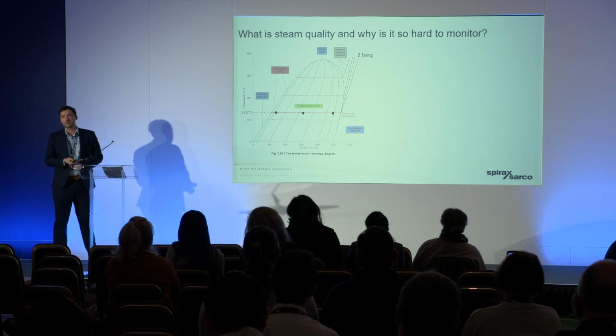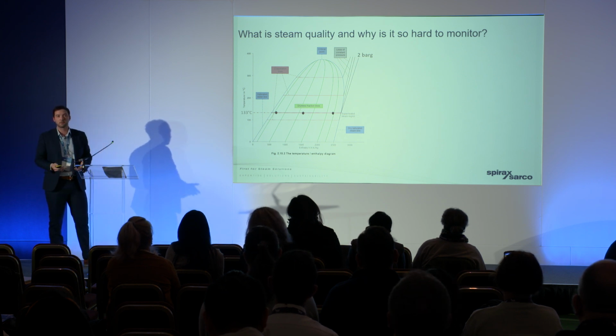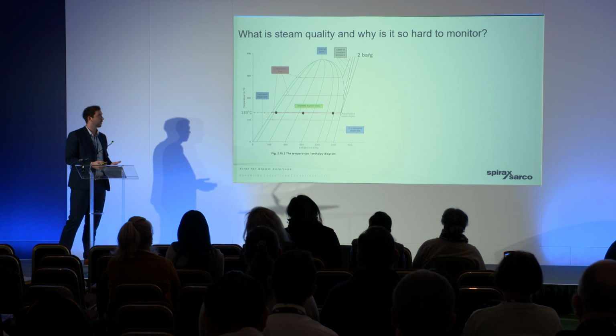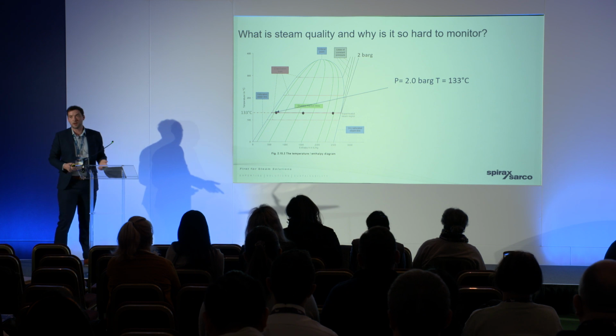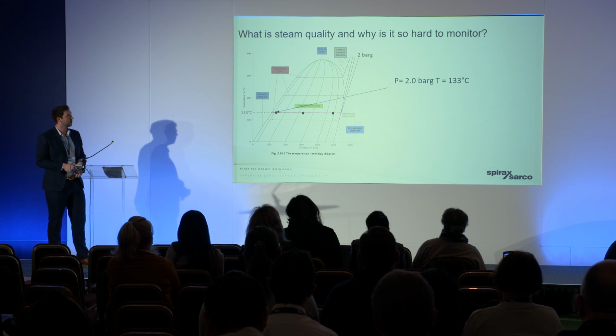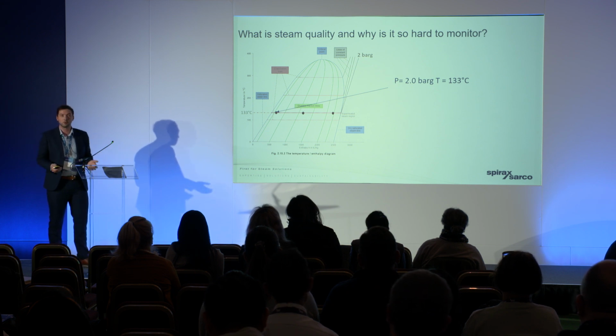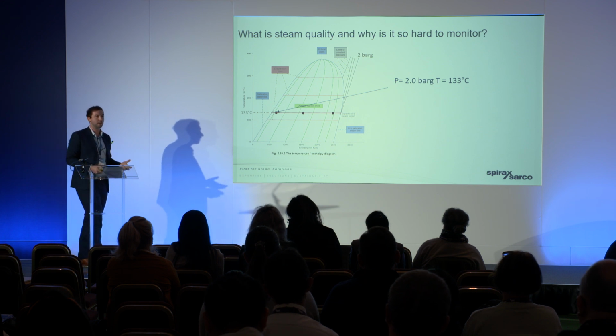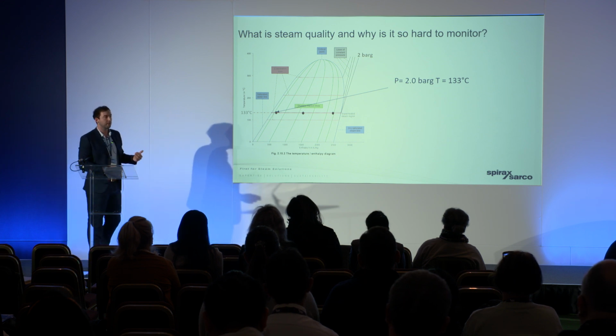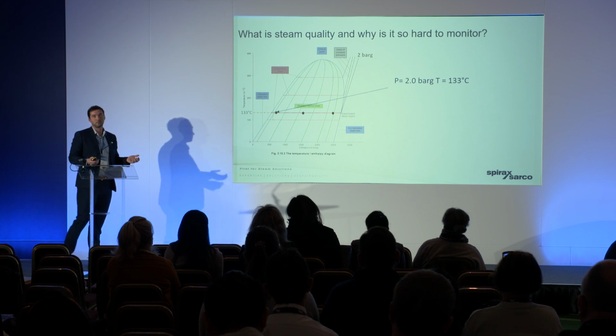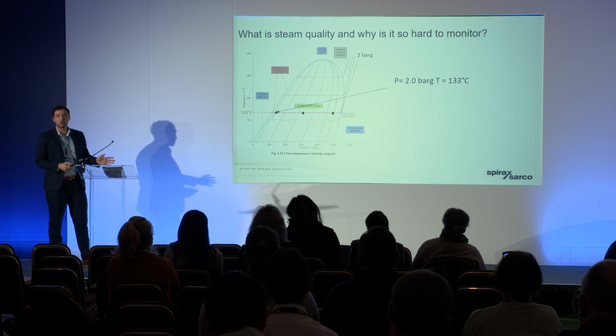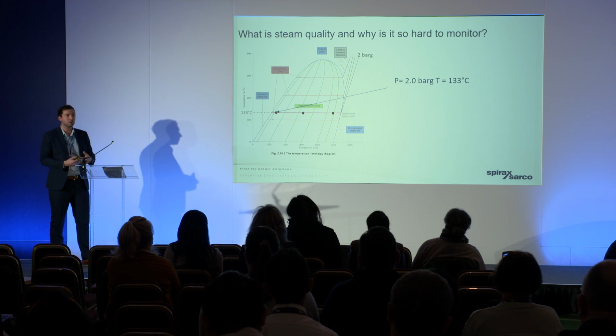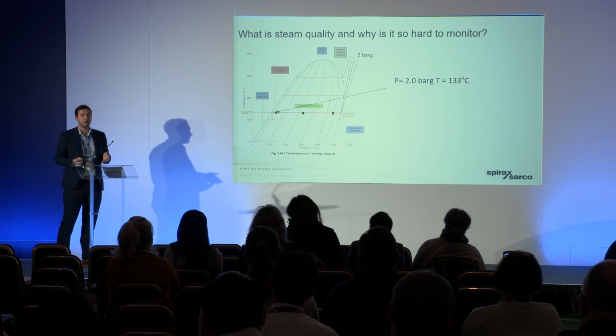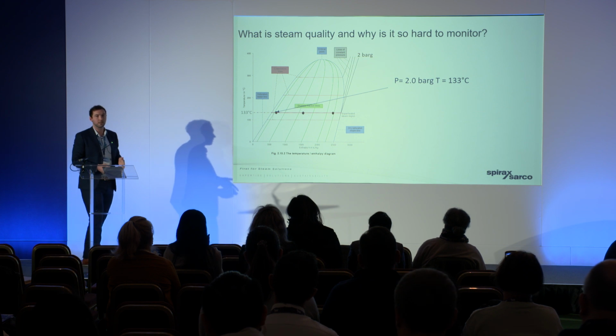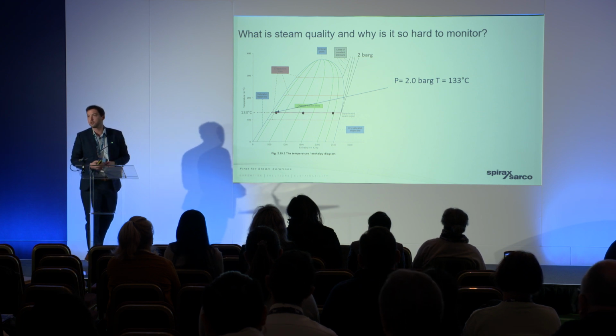So steam quality is our measure of how dry the steam is, how much of a gas it is, okay? Because at that pressure and that temperature, 2 bar, 133 degrees C, we can actually be fully liquid. We can be entirely water. This is when we talk about boiling water at 100 degrees. Water can be 100 degrees and fully liquid, okay? When we talk about quality, it's a measure of how much of that water has evaporated. In an ideal world, we want to be using steam that's 100% a gas, 100% dry.